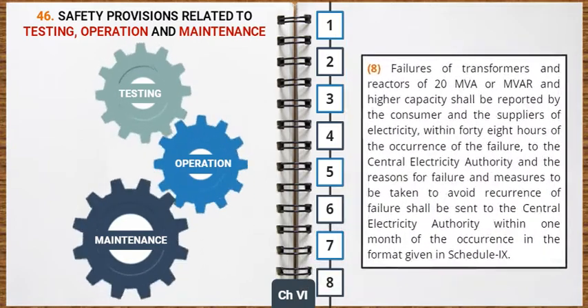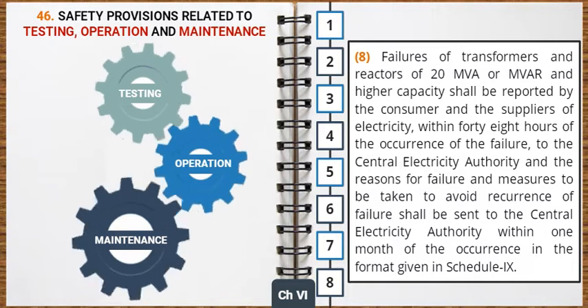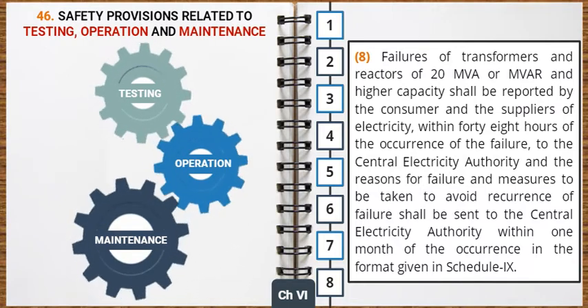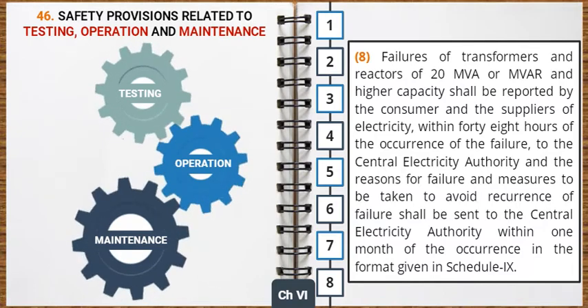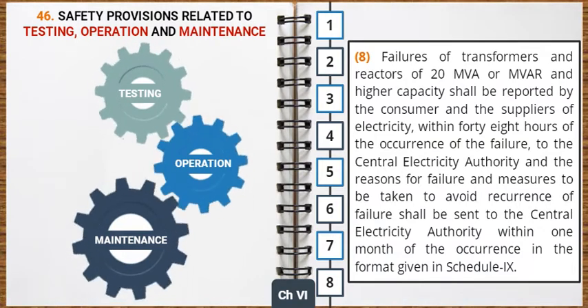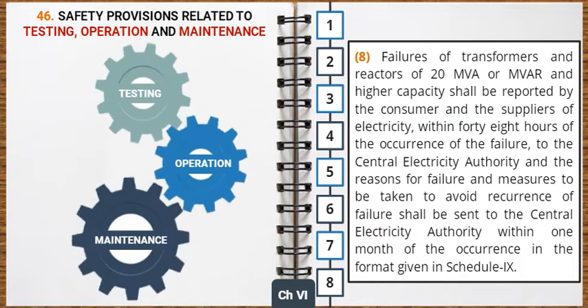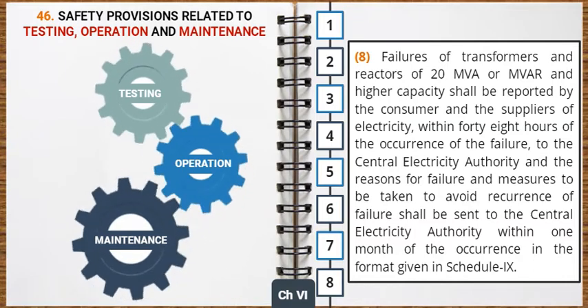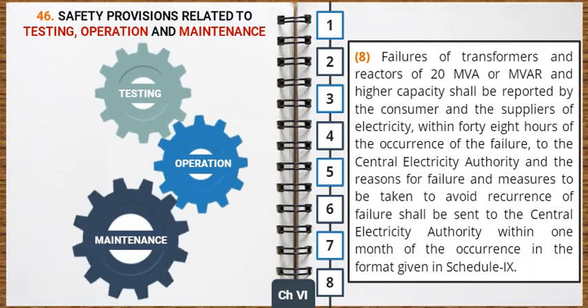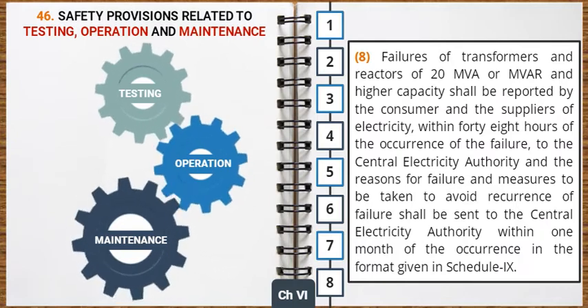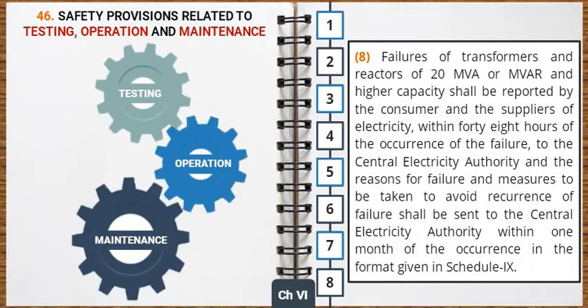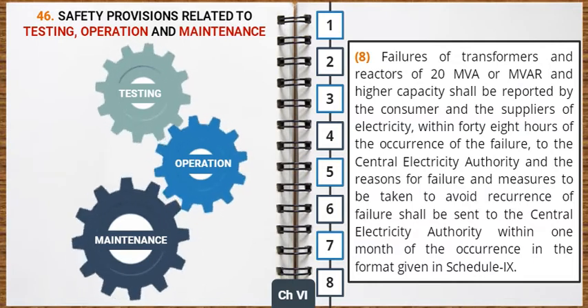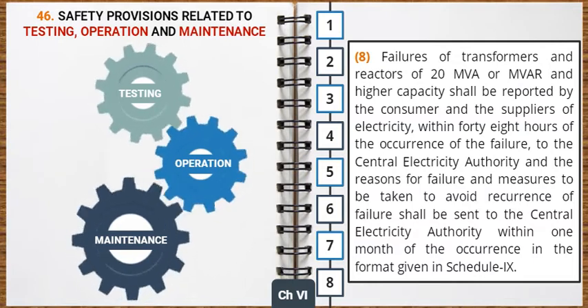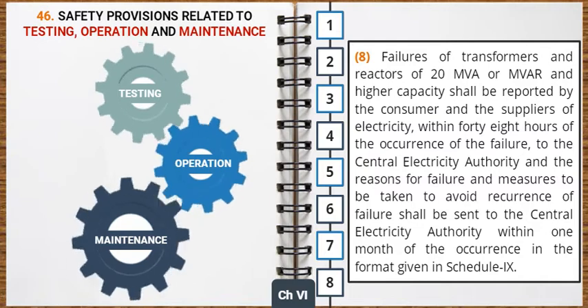Failures of transformers and reactors of 20 megavolt ampere or MVAR and higher capacity shall be reported by the consumer and the suppliers of electricity within 48 hours of the occurrence of the failure to the Central Electricity Authority, and the reasons for failure and measures to be taken to avoid recurrence of failure shall be sent to the Central Electricity Authority within 1 month of the occurrence in the format given in Schedule 9.